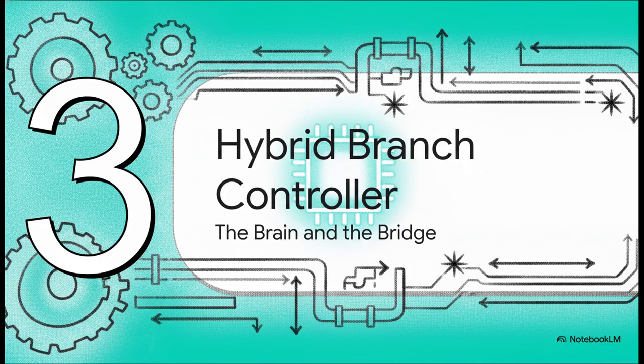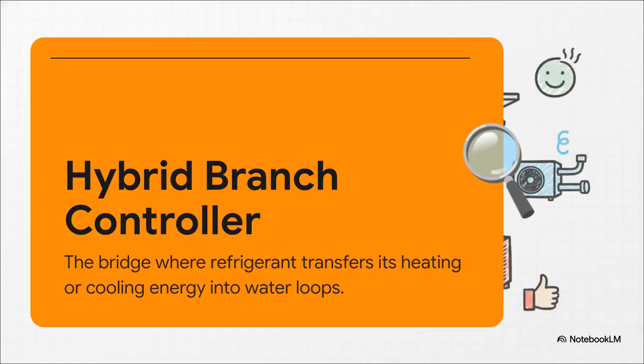Now let's head inside to the mechanical room for Section 3, the hybrid branch controller. Okay, pay attention to this part, because this component is the absolute star of the show. This controller acts as both the brain and the bridge of the entire operation. Inside this very specific component is where the refrigerant safely transfers its heating or cooling energy directly into the water. To make this magic happen, the hybrid controller actually houses 2 small pumps, specifically dedicated to serving the hot and cold water loops. This right here is the exact boundary line. It's where the refrigerant stops and the water begins.